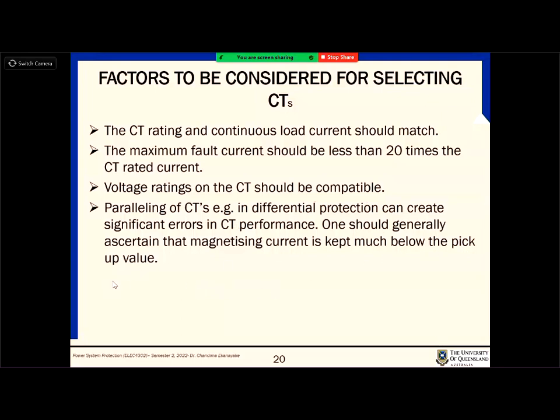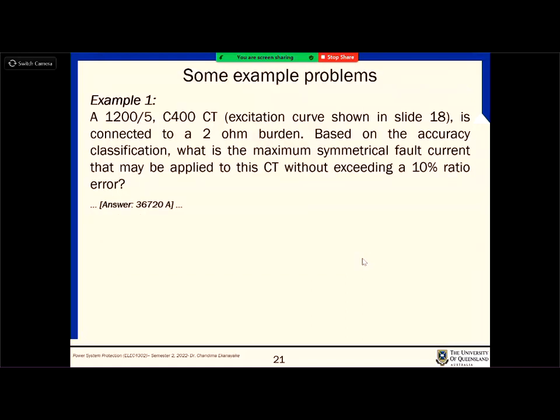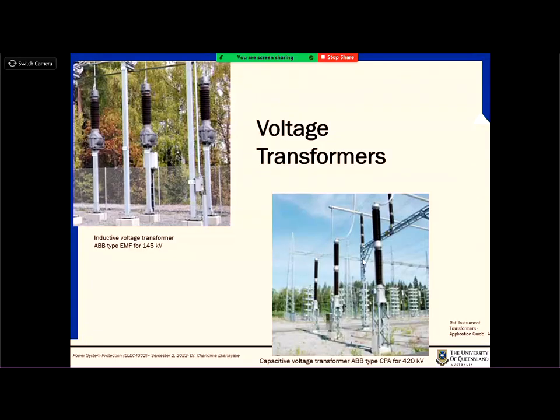See, the pickup value should be much higher than the magnetization currents. Otherwise the magnetization current is the current difference. And if the pickup value is comparable to the magnetization current, then you will have that current difference, right? So that will lead to a sort of wrong operation of the relays. Yeah, so these examples I will cover on Friday.